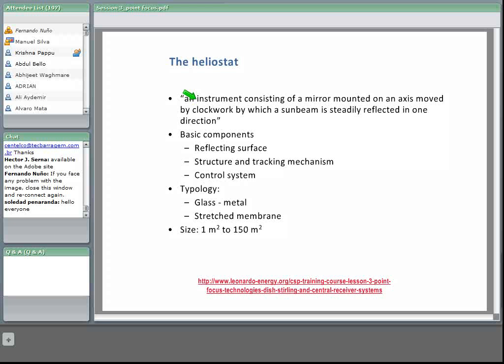There are two basic types of heliostat. One is the glass-metal heliostat — the traditional heliostat, and state of the art nowadays. The other is the stretched membrane, which consists of a membrane mounted on a circular frame or ring. The reflective surface is provided by a reflective film or thin glass mirror attached to the front membrane. These stretched membrane heliostats were developed a few years ago; at the moment they are not on the market, but could be an alternative in the future.